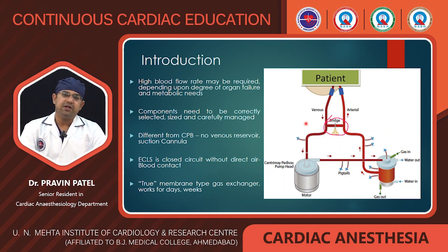What is the difference between ECMO and CPB? The one we use day to day in our life, CPB, has a venous reservoir, suction cannula, and also the cardioplegia system. But ECMO doesn't have a venous reservoir, suction cannula, or cardiotomy or cardioplegia system.